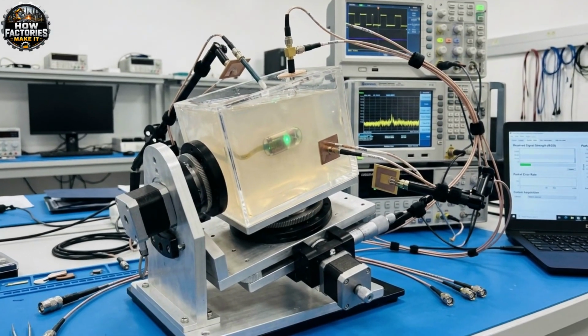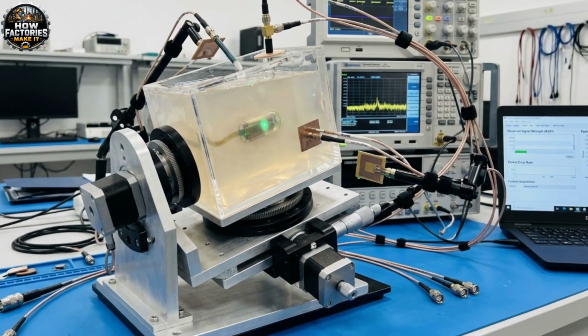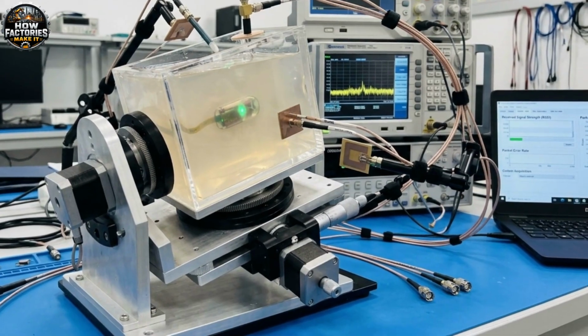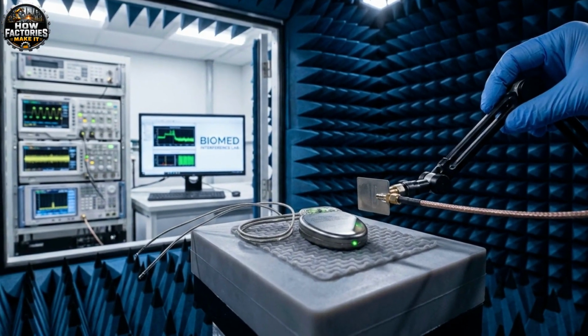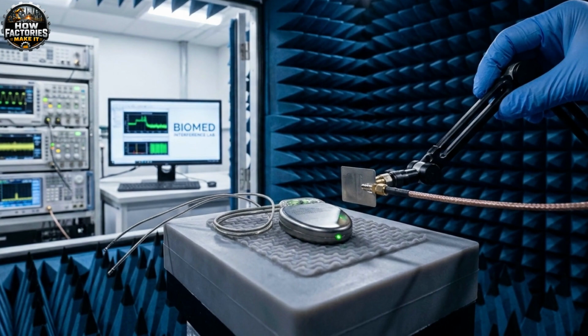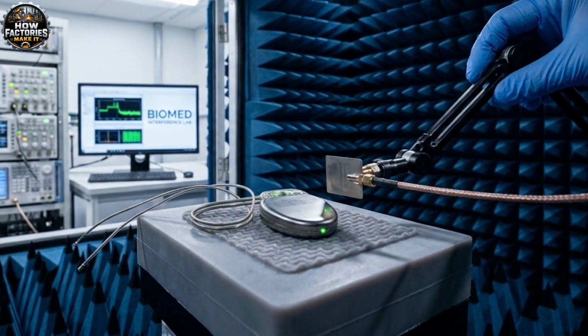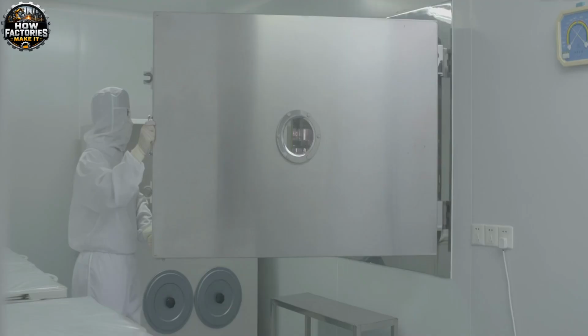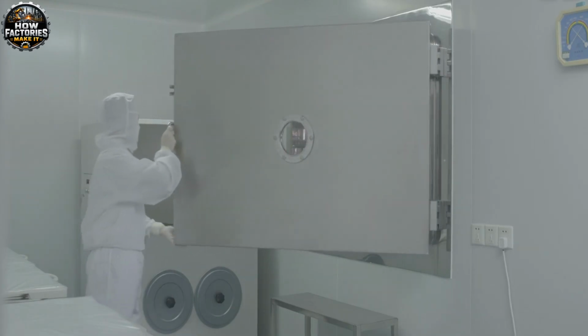Software safety systems monitor temperature, voltage, and unexpected electrical activity. If a reading moves outside its permitted range, the system can reduce power or shut down selected functions. Once the implant passes functional testing, it enters the medical device preparation stage.